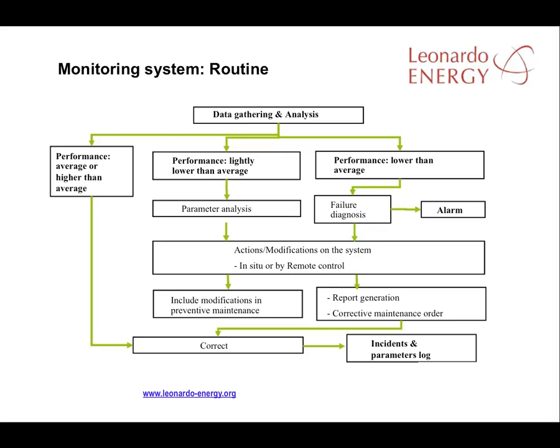Here is an overview of how the typical routine for a monitoring system appears. Once the data has been gathered and analyzed, the level of performance of the PV facility is known and decisions can be made on whether corrective action is needed. If performance is slightly lower than average, we should analyze all the parameters in the solar plant, especially those coming from the inverters, and take all the actions or modifications the system needs to improve these parameters. These modifications can be done remotely or in situ, but usually it is necessary to have staff in the PV facility. All modifications must be included in the preventive maintenance plan to ensure they are undertaken periodically to improve plant performance.